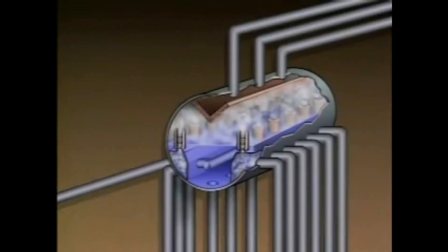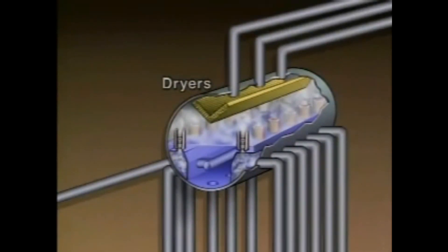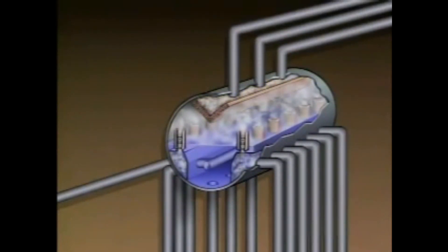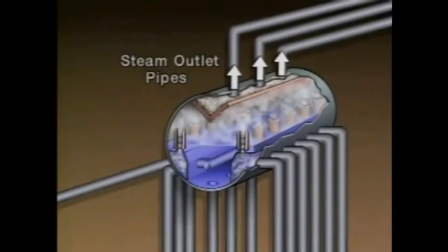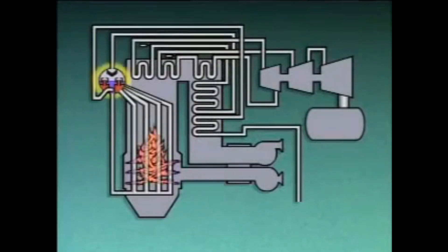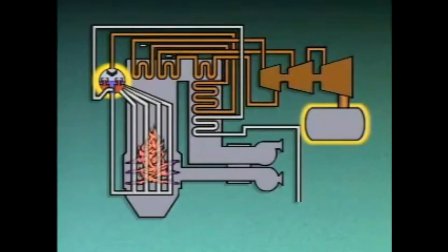The steam rises into the upper part of the drum. The steam could still have some water mixed in with it, so in this example it is sent through dryers, which are located in the top of the drum. The dryers remove as much water as possible before the steam leaves the drum. This is important because water that flows out of the drum with the steam could damage downstream components. The steam is discharged from the drum through steam outlet pipes.